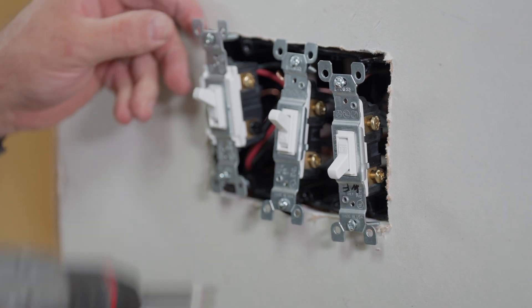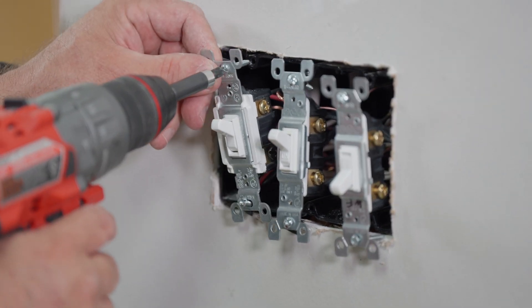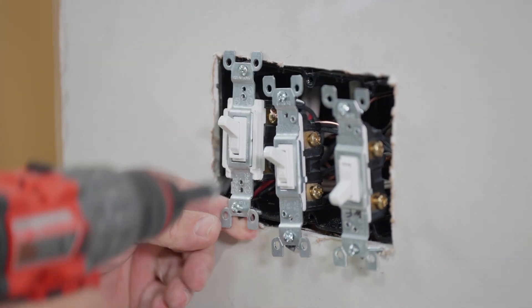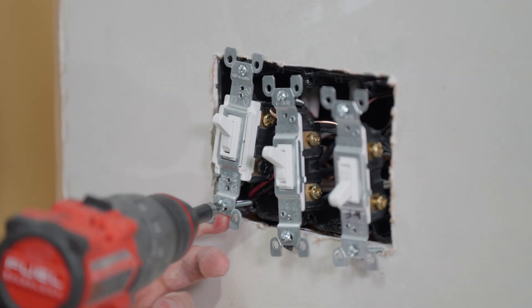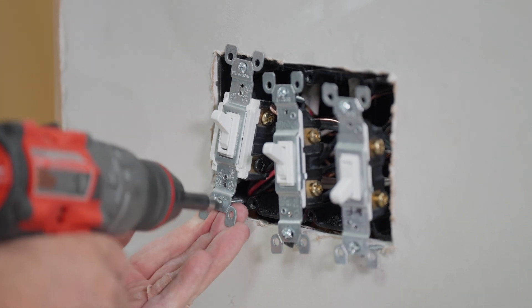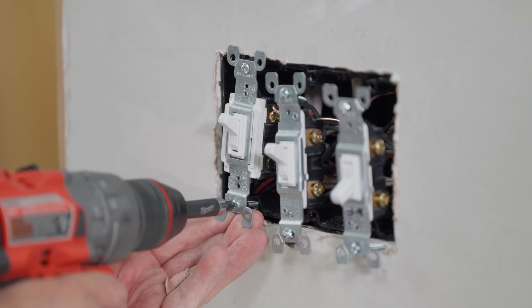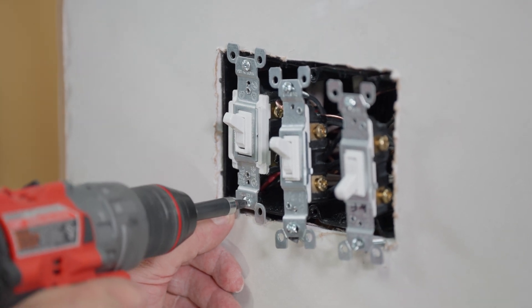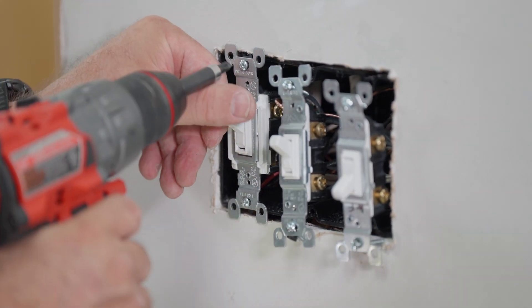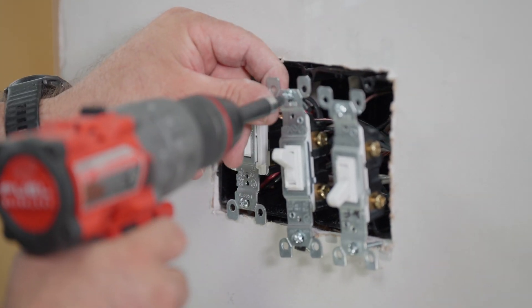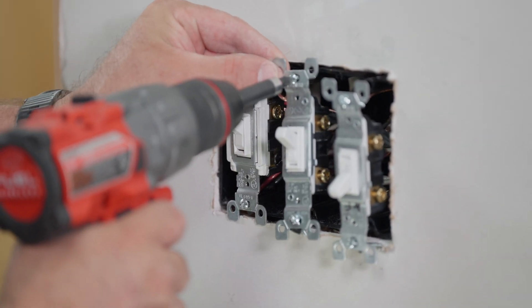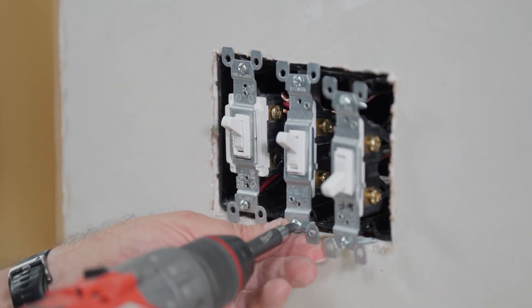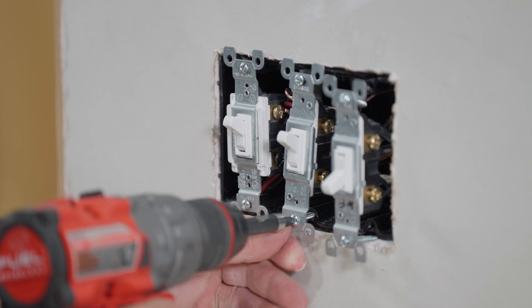You also have to be careful when you're screwing each one of these in that you don't over tighten it. This is a plastic box and it's really easy to strip the box out if you're too fast, too much pressure. You want to make sure you get in there and tighten it up. So what you'll find these plastic boxes move around a little bit. You may tighten this first switch up but by the time you get to the third switch the box has pulled out of the wall more. So you'll have to go back and tighten each one.